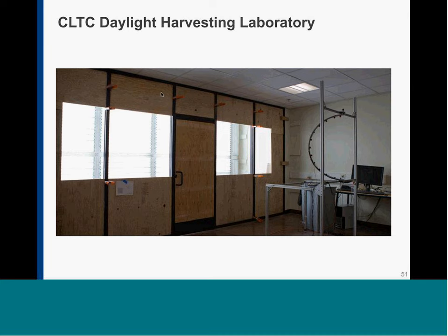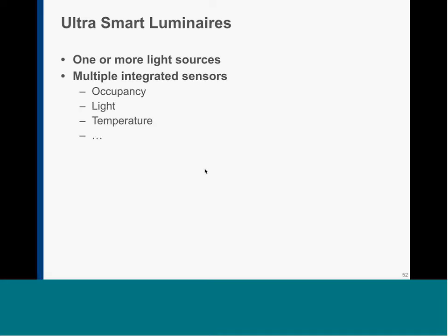They have communications, and they communicate both with other luminaires, with utilities, as you will see on my last slide, also possibly with windows. And the control logic is based not only on their own sensors, but also on the sensors of the neighboring luminaires. So smart luminaires have their own brains, they have their own sensors, and they can automate their operation on their own, trying to best understand what's happening, not only based on their experience with the sensors, but also because they have access to the experience of their luminaires in the space.